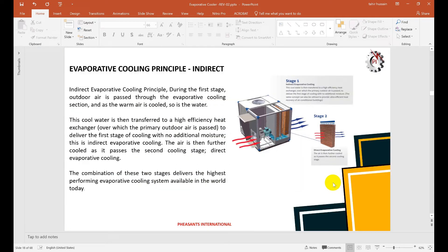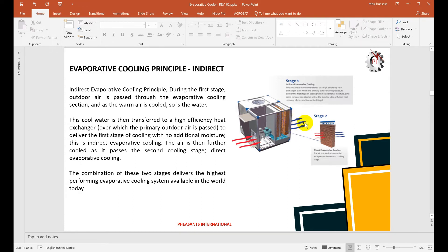In the indirect evaporator cooling system, hot air enters, but a cooling tower is used to cool water. This cool water is pumped to a heat exchanger coil where hot air passes through without any moisture addition — only sensible heat is reduced. After this coil, there is a conventional evaporator section with cellulose pads where moisture is added and cold air is produced. This indirect evaporation cooling system can be two-stage or three-stage, like a hybrid system.